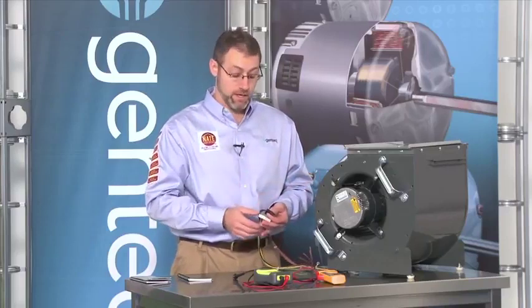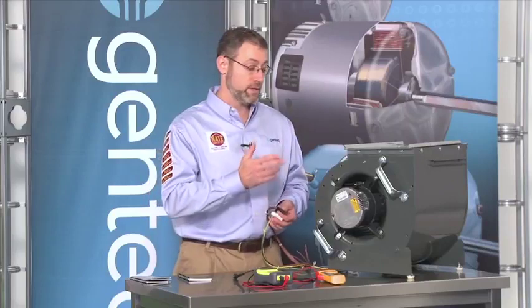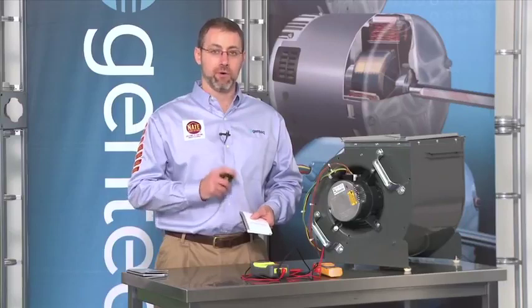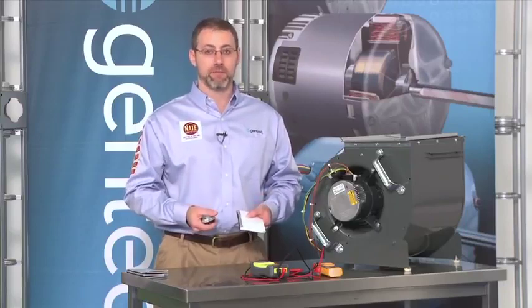I've already confirmed that I have high voltage going to the motor, so from this final check, I now know the motor has the voltage it needs to operate, and it's getting the communication it should have to tell it when to turn on. If the motor is not running at this point, it's a failed motor. So to summarize troubleshooting the X13 motor, there's really just two inputs to the motor: high voltage and low voltage. The high voltage power is always on the motor whether there's a thermostat demand call or not.